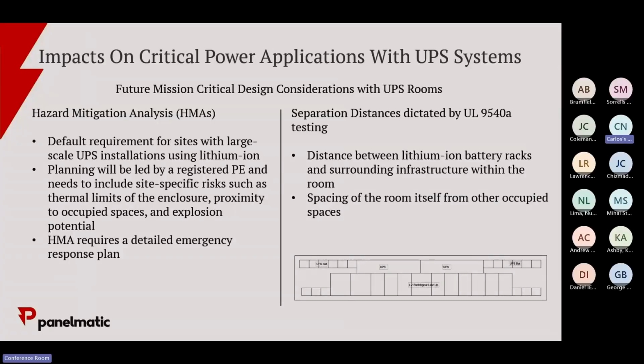It was a giant field with hundreds of containers out there. But you hit the nail on the head - the HMA analysis was done in conjunction with the electrical, fire suppression, and structural engineers because it had deflagration panels. So that HMA plan, while it says a registered PE, really covered multiple trades working together to sign off on that stamp. It doesn't specify which division has to be the one that actually puts the PE stamp on it, but usually they're all very closely working together to get to that stamp.